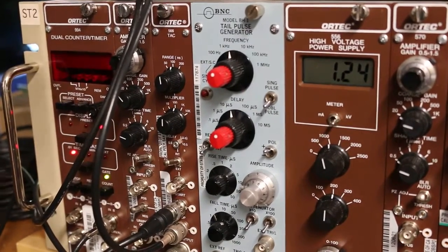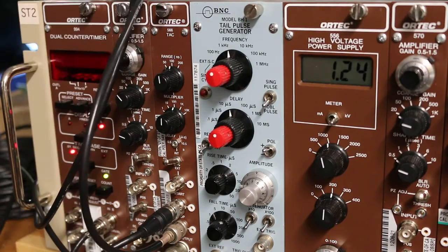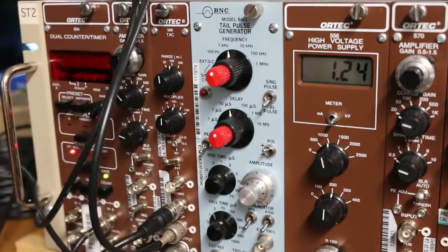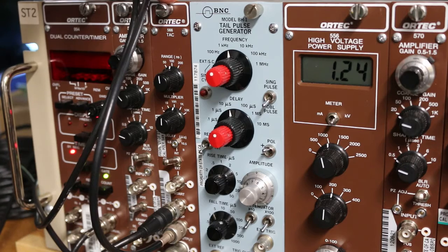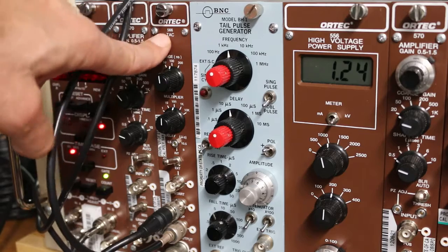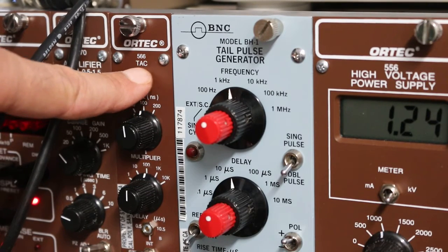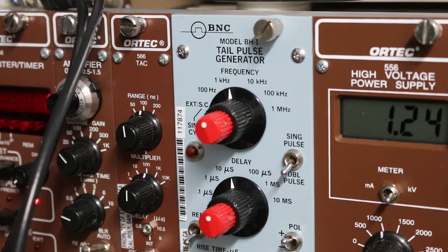Well, what we do is go to one of my personal favorite NIM devices in the whole bit here, and it's this one right here. And as you know, when I say NIM devices, there's amplifiers and SCAs and high voltage power supplies and counters and timers and all those things that you can slide into this NIM crate here. The time amplitude converter is one of my favorites. So the first thing is, let's just think about what it says here. TAC. It's the 566 TAC, and TAC stands for time to amplitude converter. So you have to think very carefully what this device does, a time to amplitude converter.